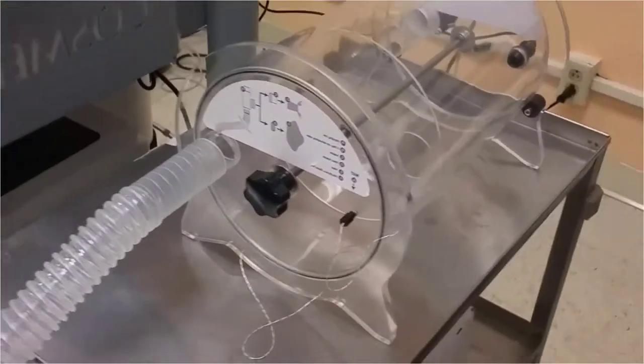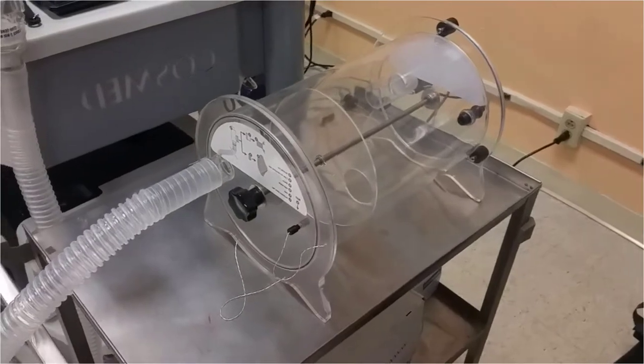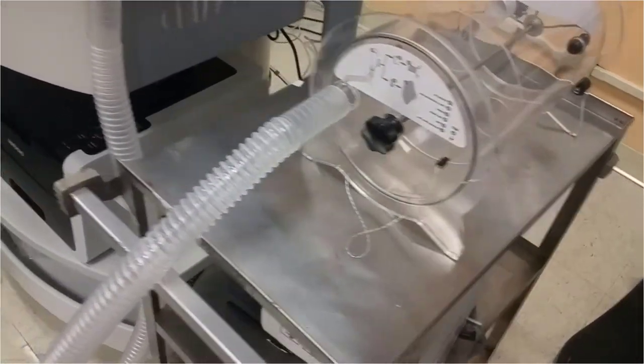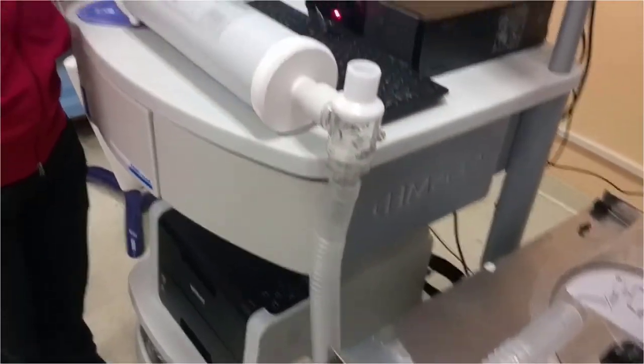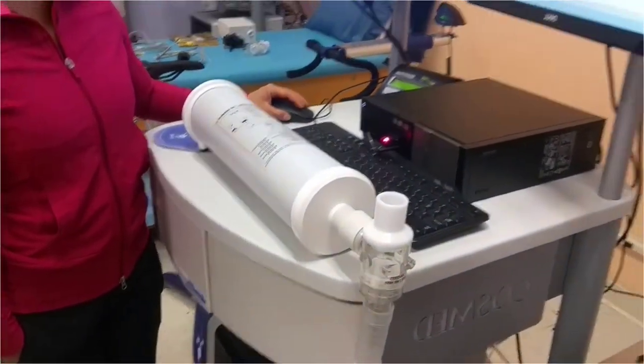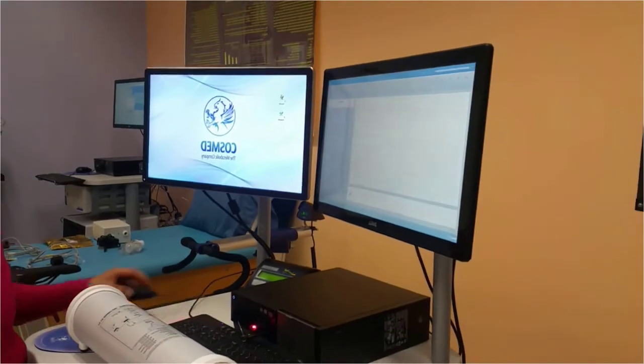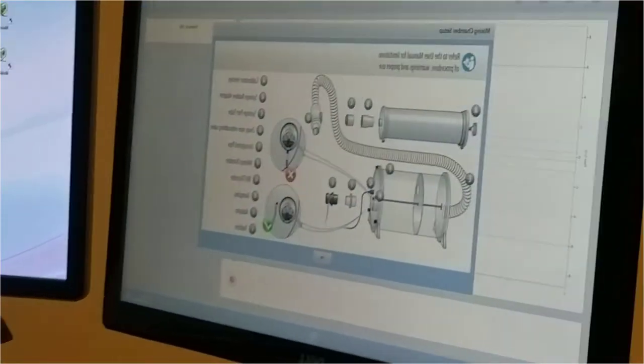And it wants 6 full respiratory cycles, just like the other one, but you're not going to see inspiratory flow. You're only going to see the expiratory flow. You're using the dongle, you have the 28mm turbine. Yep. Good. And, oh, directions, there they are. That'd be great. Okay. So the green light's on, so you're good to go.